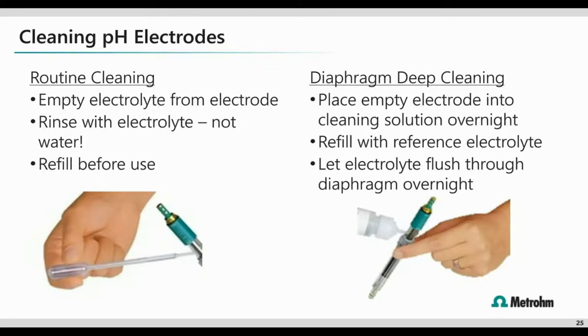With the deep cleaning, this may be required if the diaphragm has become clogged, and the electrode may require a deeper cleaning. If you've got a sample that might have wicked up into that frosted glass area of the electrode, this might be helpful. What you're going to do here is empty the electrolyte out of the body of the electrode and place the sensor into a cleaning solution overnight. Let it sit overnight. The cleaning solution will have wicked up into that diaphragm, but not up into the chamber. The next day, fill the chamber with the proper electrolyte solution and leave the spill port open. We want the electrolyte to drain and completely flush that diaphragm back out.